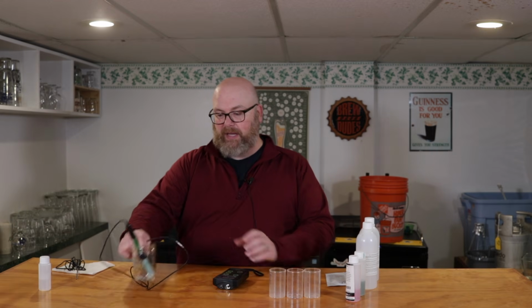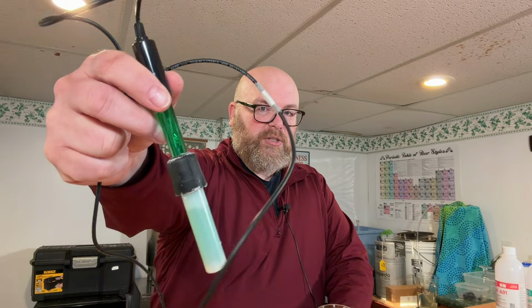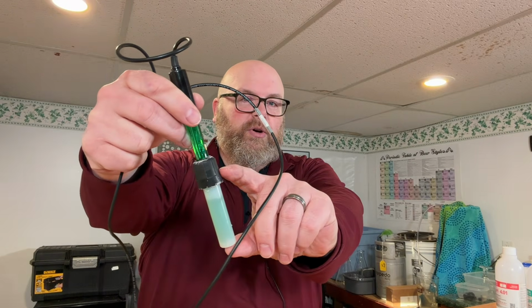So that's convenient. So I'm going to go through the parts of what I use to measure pH, and then I'll show you how to calibrate the meter too. So you've seen the meter. The first big thing to go over after that is the probe. So this is what the probe looks like. It's in a storage vial because you want to keep the probe moist most of the time. There's a storage electrode solution you should buy to maintain your probe in between readings.